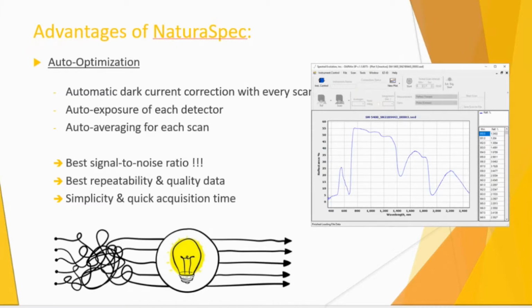And the interesting thing with the NaturaSpec is that this dark current correction is done automatically. There is a shutter in the instrument that, with every single scan you take, is going to compensate for that dark current noise. So you never have to worry about that. It's done automatically. There's no optimization step for dark correction. And same thing with the exposure.